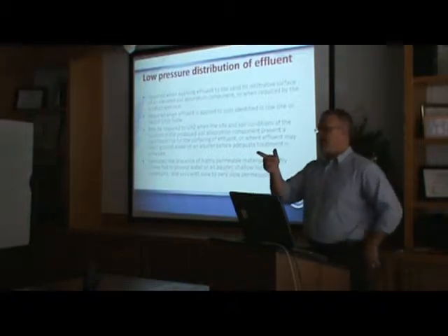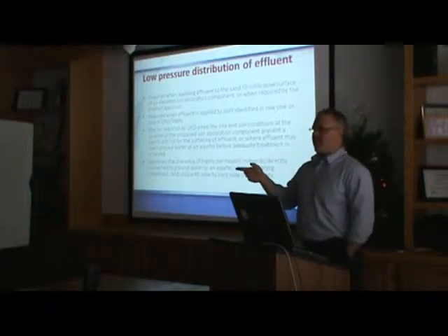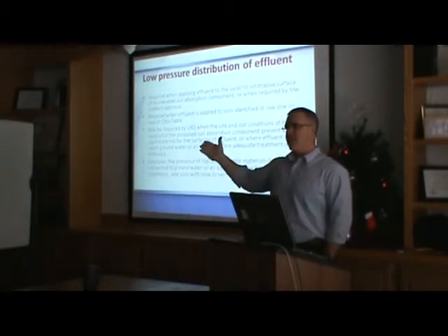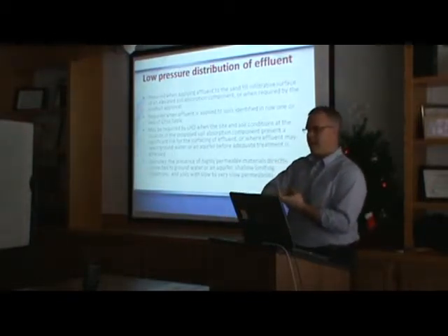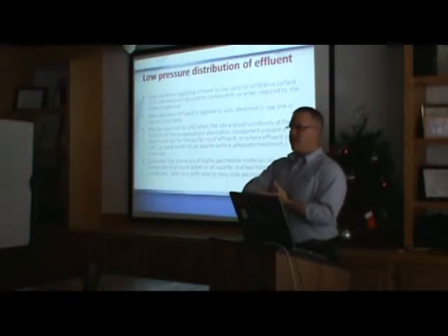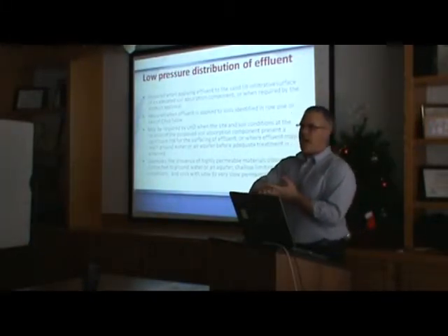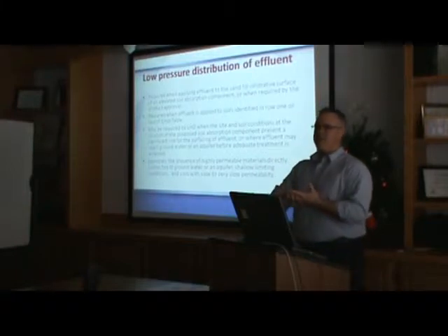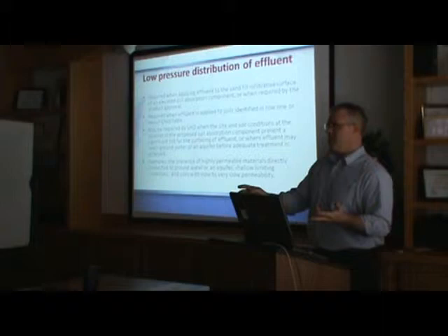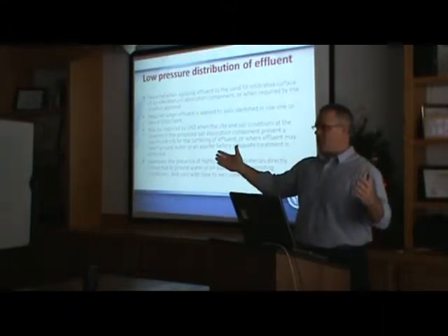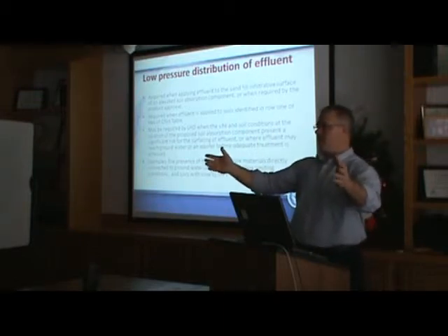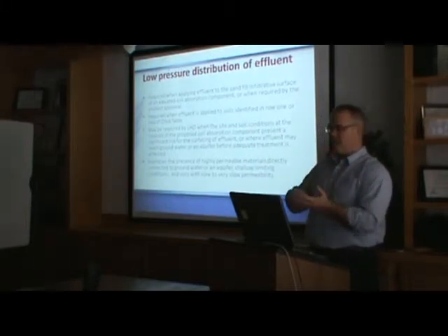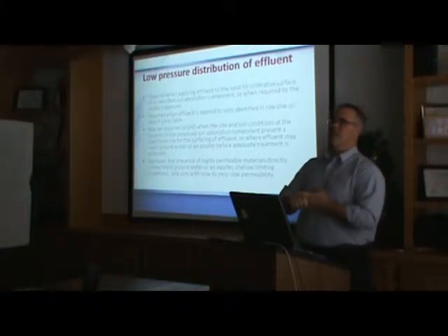Jim, maybe let me explain a little bit about flood dosing. In 2007, most of the state, including the state health department, were ill prepared. What they basically said is if you had an aerator, this is the most common problem we had, you needed to equally distribute effluent across the surface of the trench. And the only option they gave you was LPP. Bingo. There goes the price tag. Not only was it LPP, but there were no provisions for multi-zone valves. So you might have 4 lines of an LPP system coming after an aerator that you had to dose the entire LPP system all at one time, 100 gallons per minute, GPM, coming out of that system. That means the pump was huge, the head was high, it was expensive.